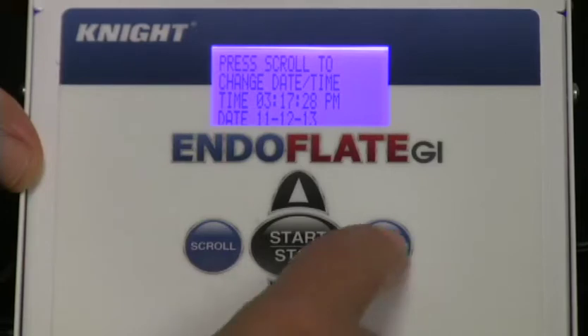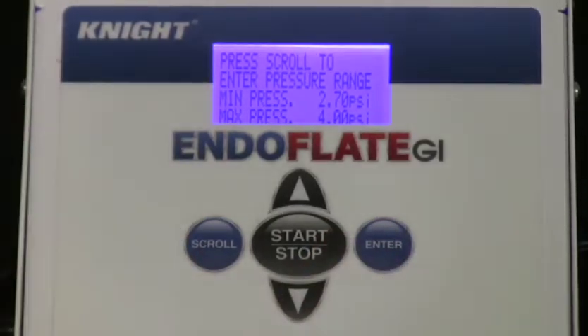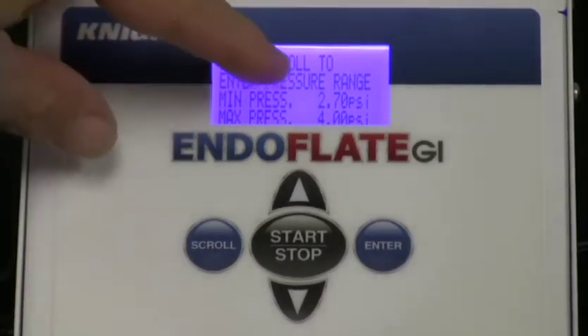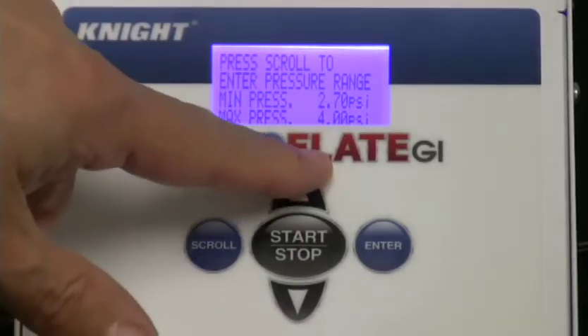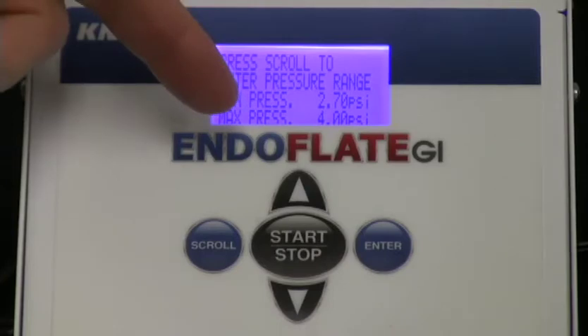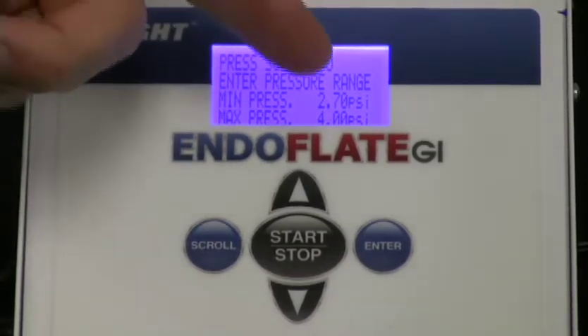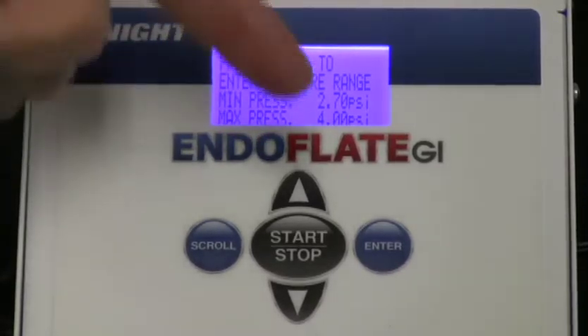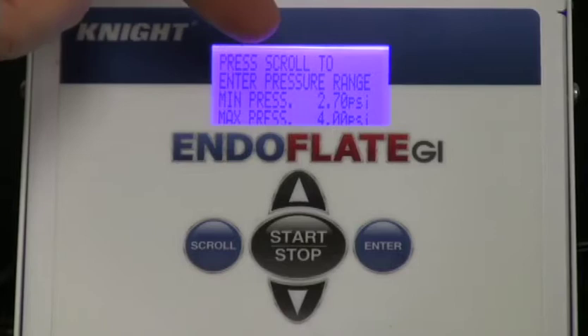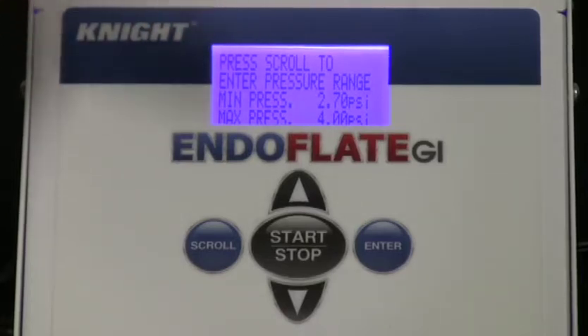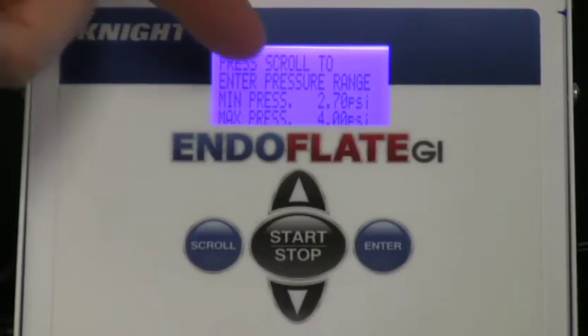Here you can change your time and your date. At this point, this is where you want to set your minimum and maximum pressure values. Now, most of the manufacturers, we're talking about Olympus, Fujinon, and Pentax, their publicized minimum and maximum inflation pressures are between 2.7 and 4 psi. Now, we've got to double check what those values are. But right now, those are the numbers that we're going to ask you to program to, unless you've got another reference to the original manufacturer's inflation values. But right now, based on the best information we have from those companies, the minimum is 2.7, the maximum is 4.0.